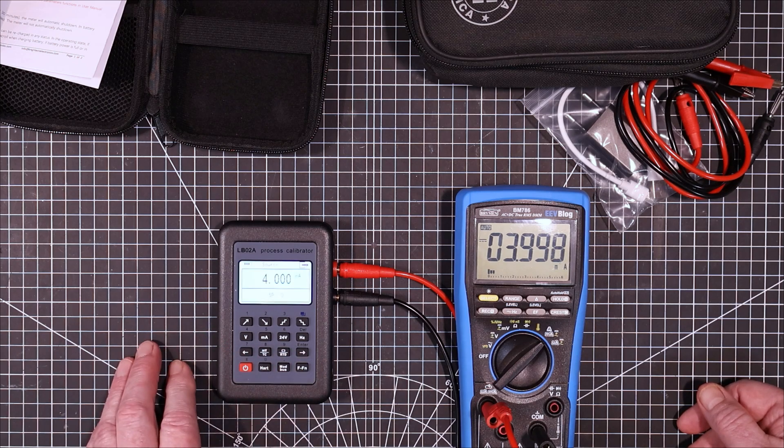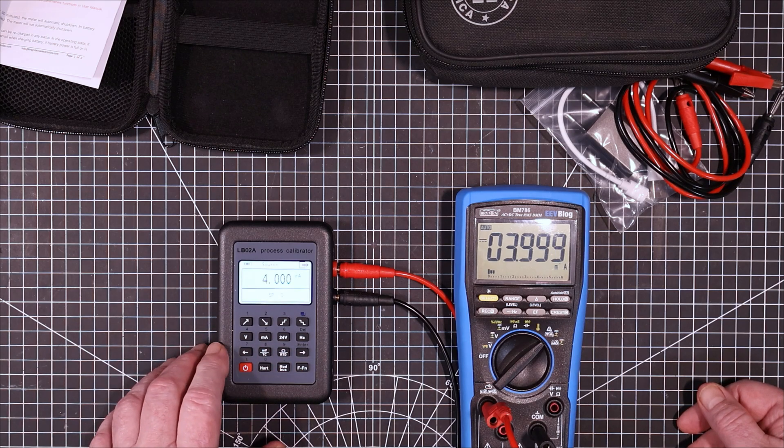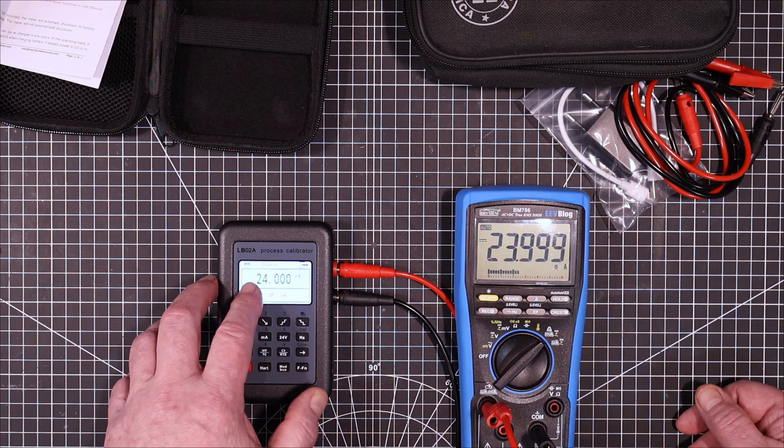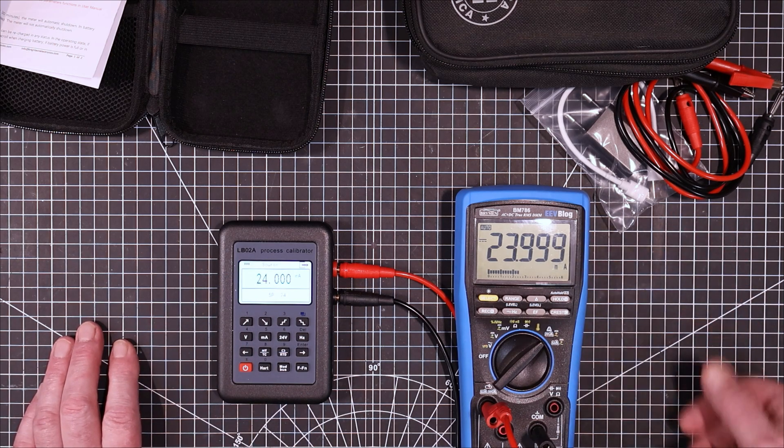And it's right on. Let's put this in full function mode here. Let's see how many milliamps can we go up to. High as it goes 24 milliamps. And it's right on.